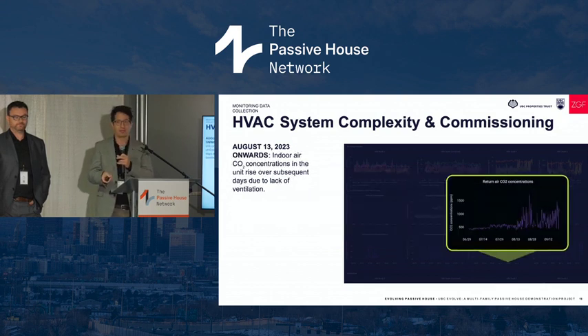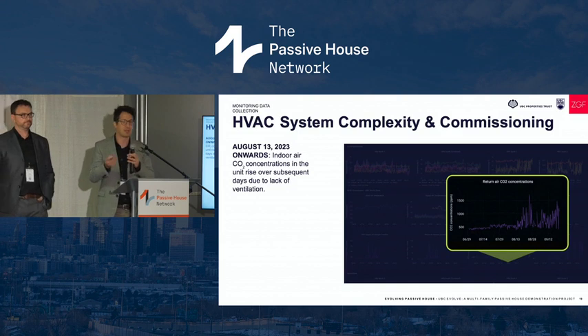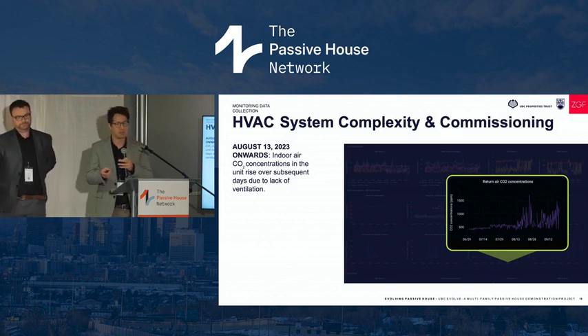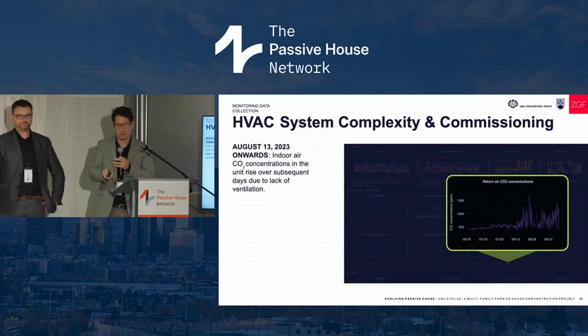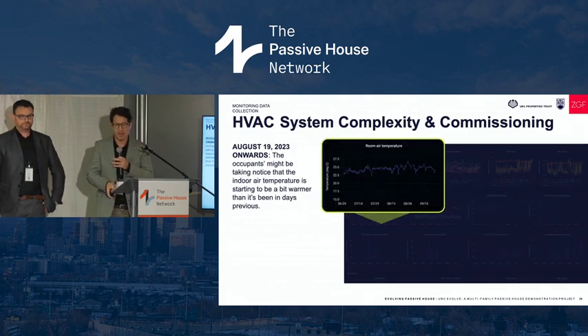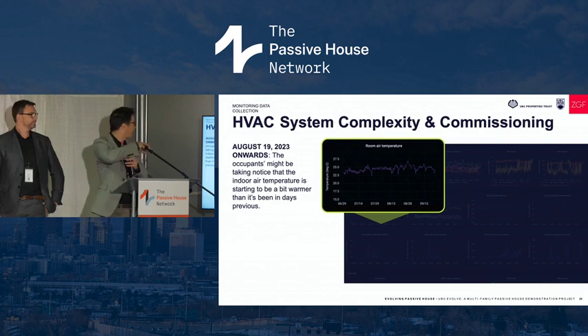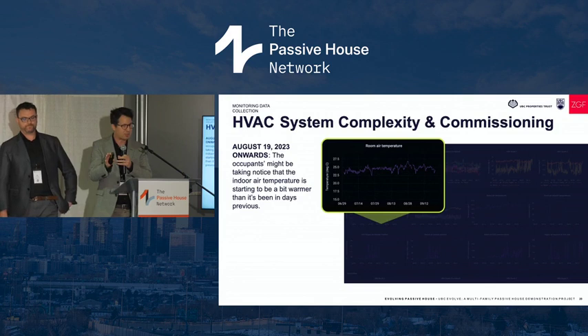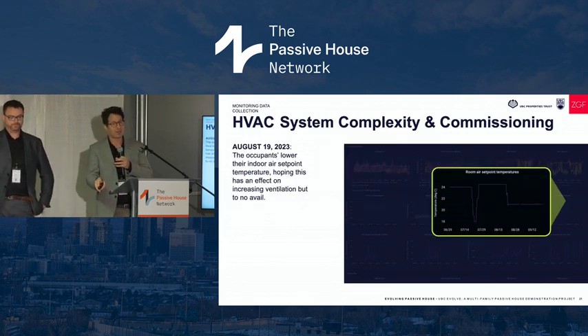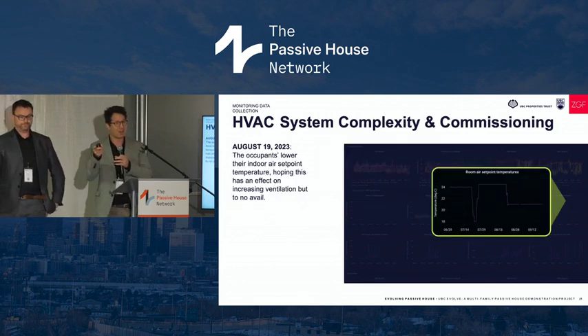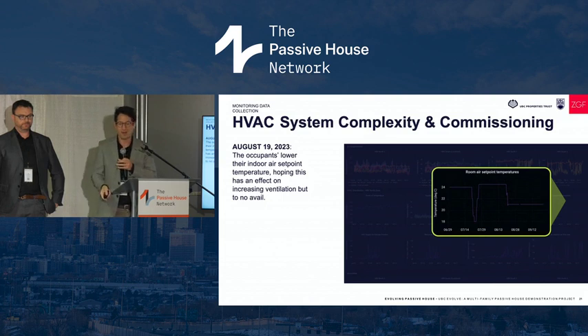In the days following, CO2 rates went up. The residents might not have been accustomed to using the windows, or maybe they had the windows open and CO2 was still rising because ventilation wasn't reaching the area where the sensor was located. Room air temperature also rose during a mild heat wave later in August, going up to about 26 degrees. You can see spikes in temperature near the end of August as residents tried to reduce their set point, hitting the button for cooler air, but nothing worked because the damper had stayed closed ever since.